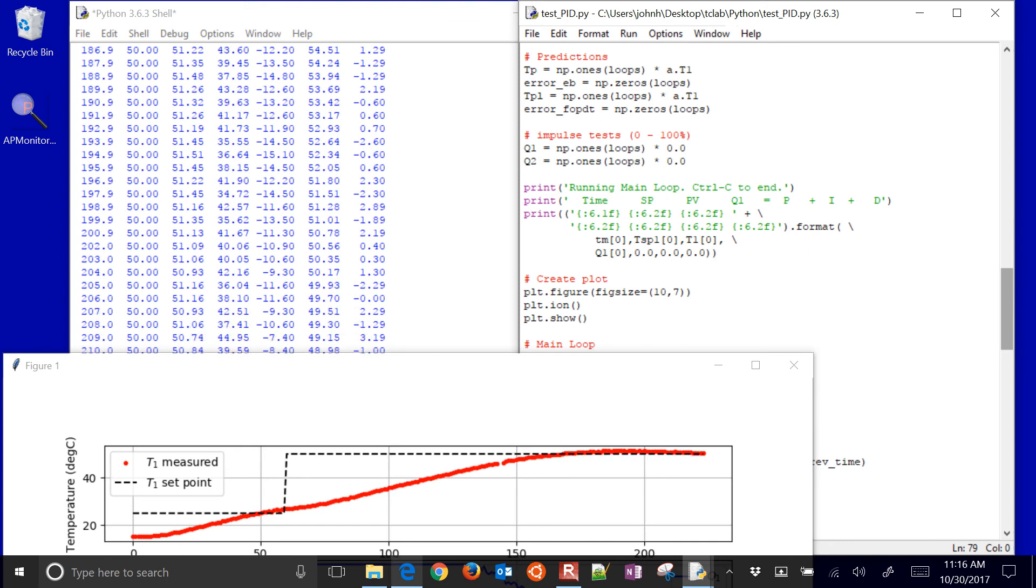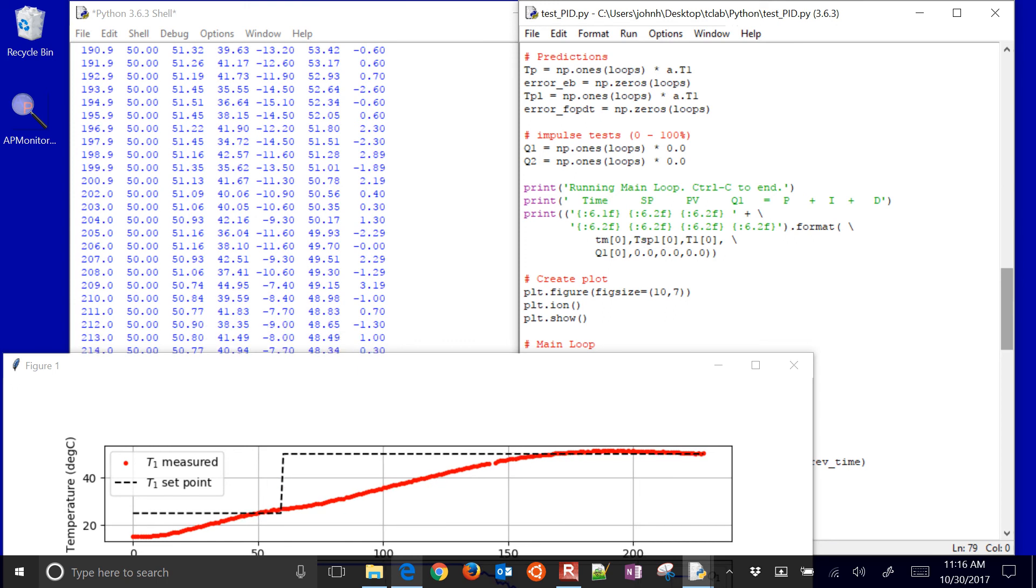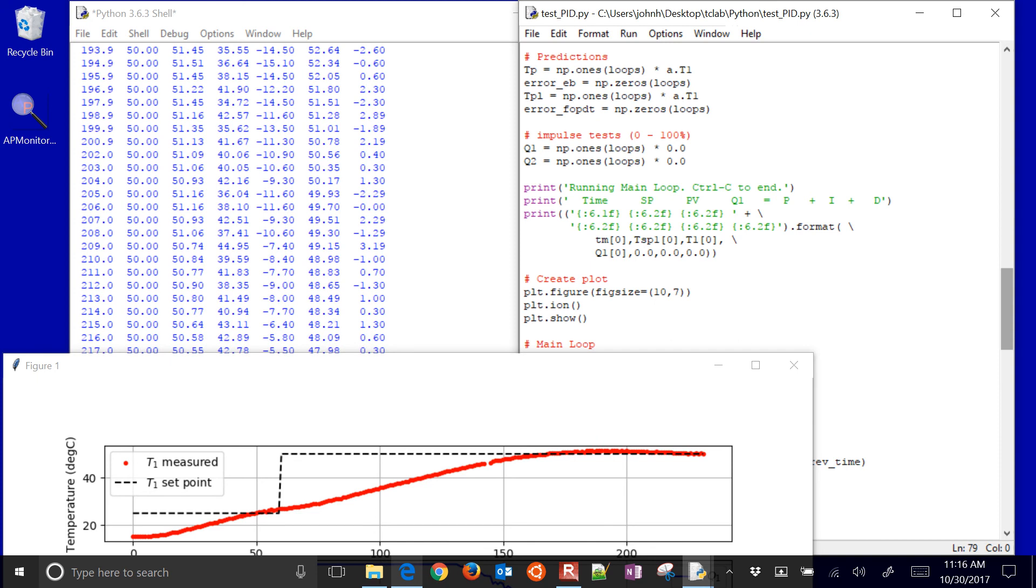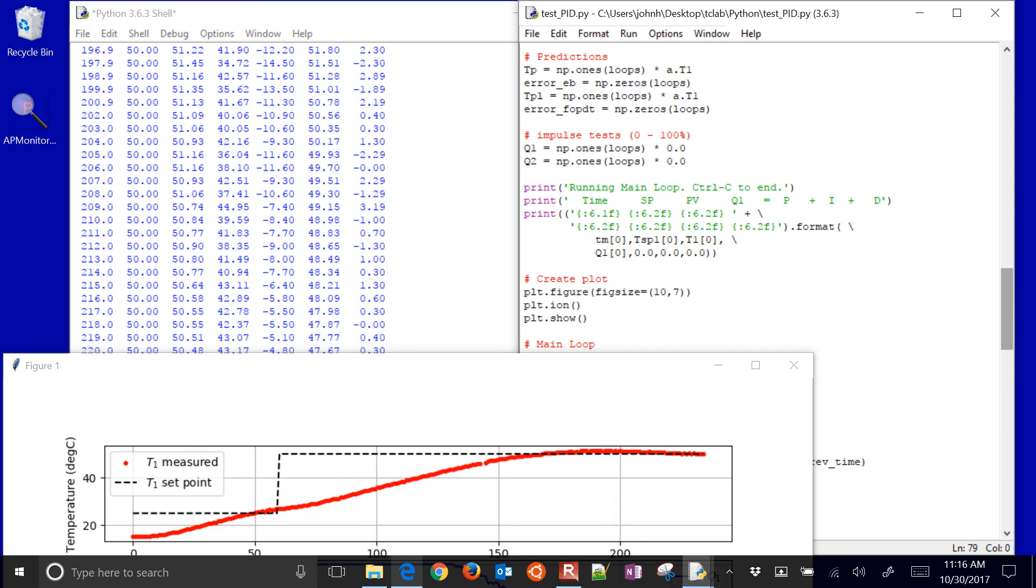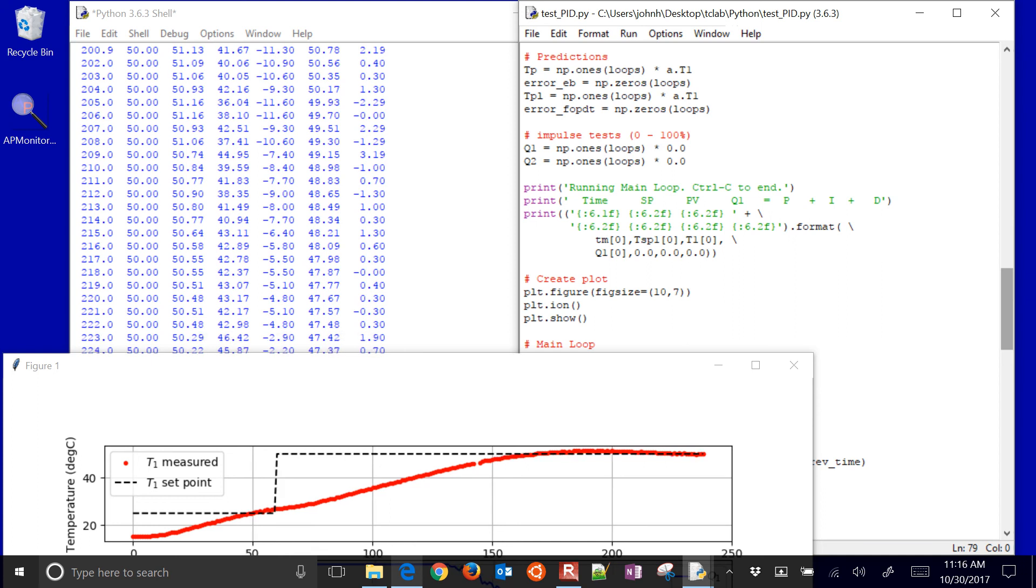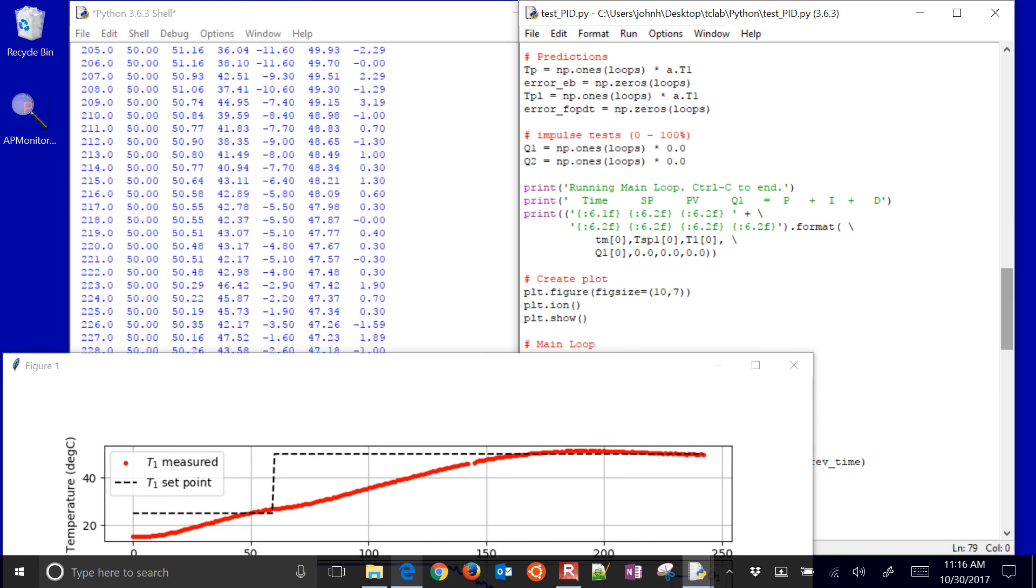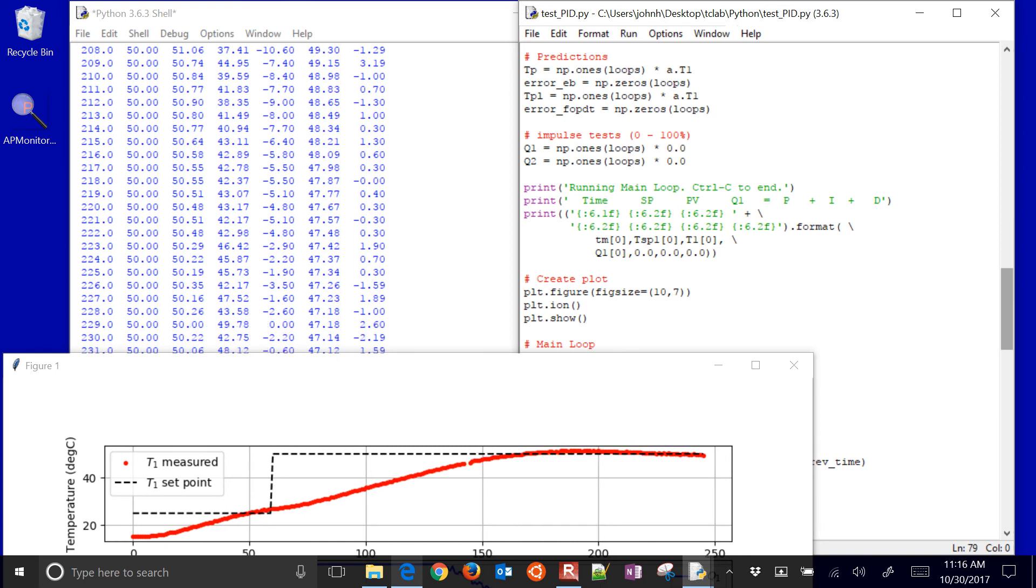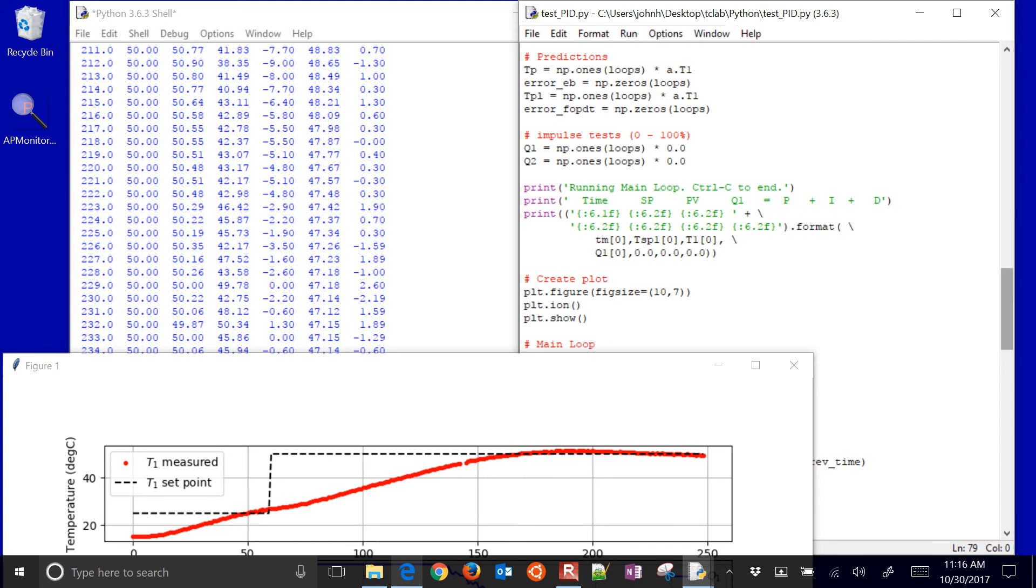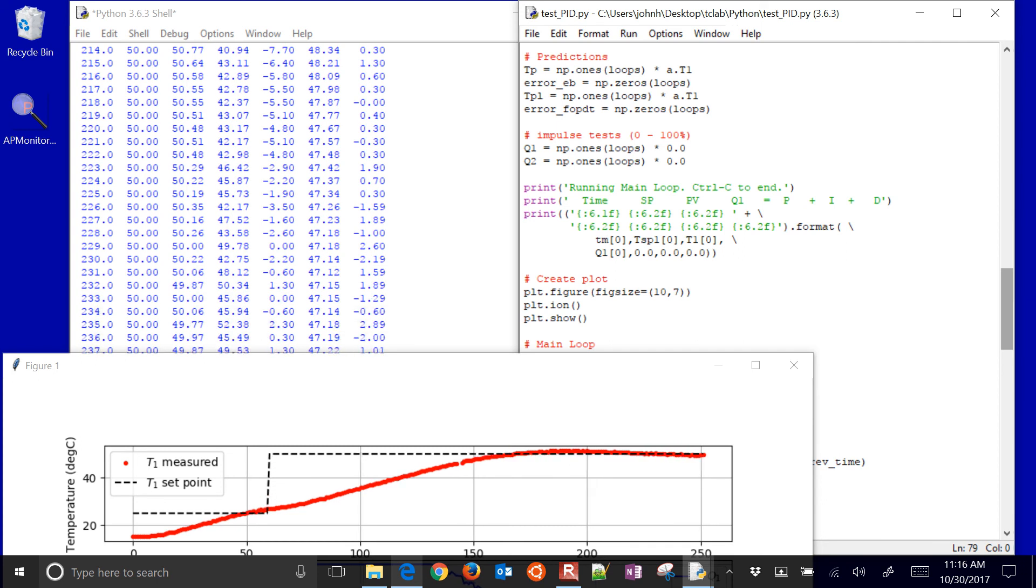They're coming in this window on the left. That is the proportional, the integral, and the derivative values. So the proportional is the first one. That's going to be Kc times my error, my set point minus PV. And then I have my integral term, and then my derivative. So you see the contribution from those three that equal the heater output, or the controller output. So that's useful to see as you're tuning the controller, trying to get better performance.